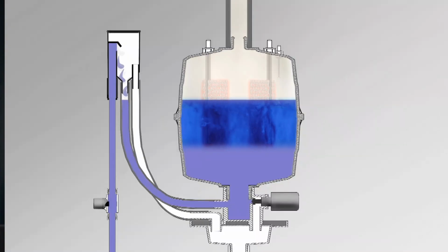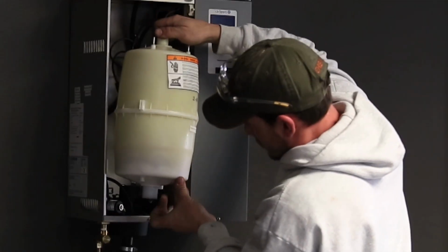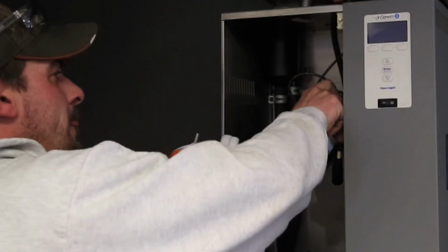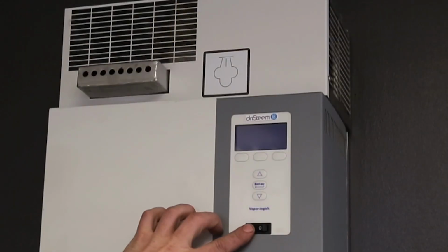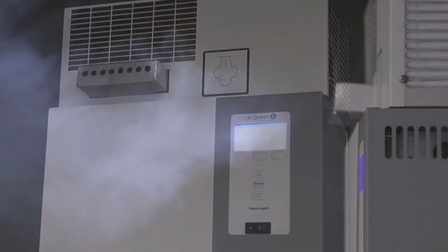With electricity, maybe it's electric resistance heaters. The benefit of those is you can dial them in right where you need to. Otherwise, you can use an electrode type, and that goes back to our conversation on maintenance. Do you just take the tank and throw it away and put a new one in? From a maintenance standpoint, that makes sense. There's a trade-off, though. When you do that type, the controllability isn't as tight because you're passing current directly through the water. So it depends on how much water is in the tank and how much of the electrodes are covered. The maintenance is simpler, but now I don't get as tight of a control.